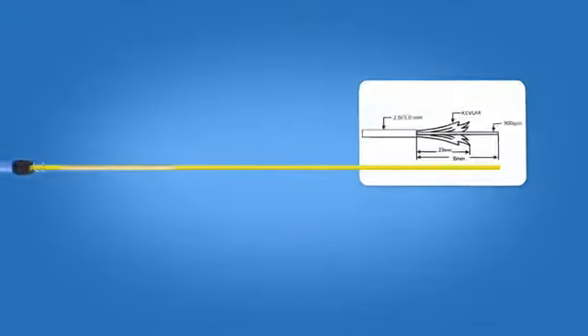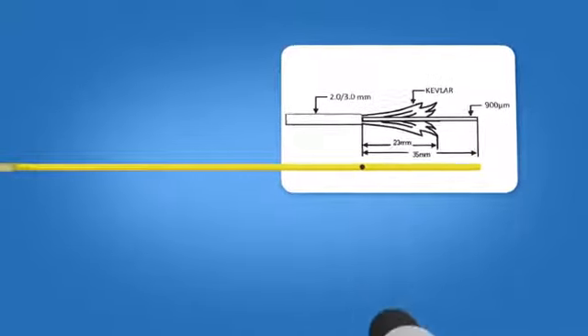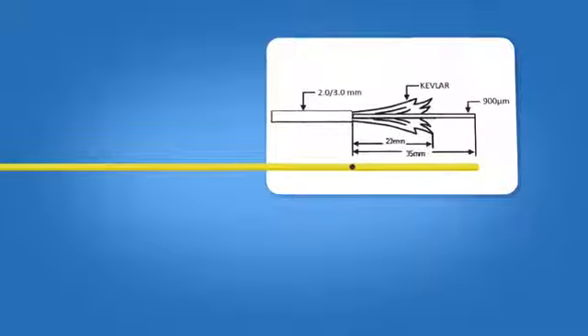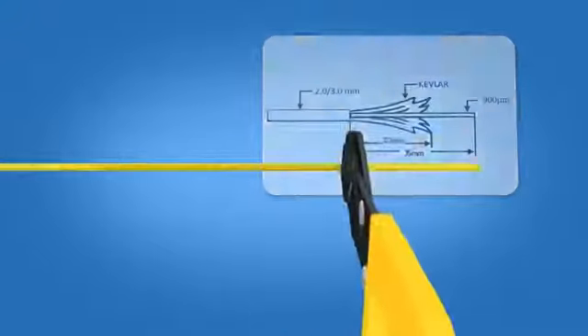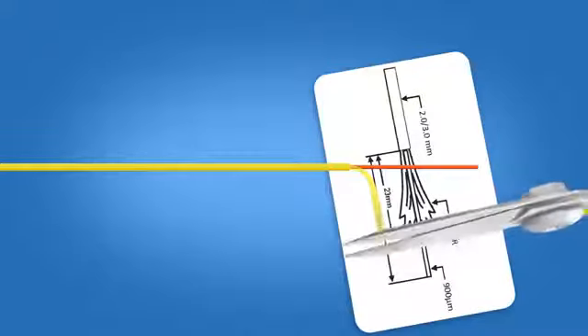Using the template on the front of the connector packaging, mark the cable at 35 mm from the end of the cable. Strip 35 mm of 3 mm jacket from the cable exposing the kevlar and 900 micron fiber. Cut the kevlar to a length of precisely 23 mm.